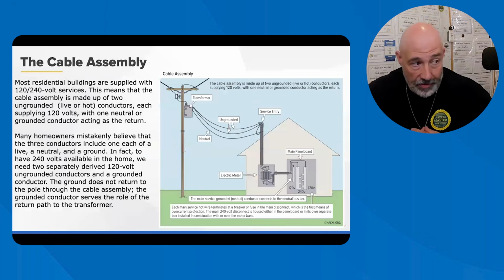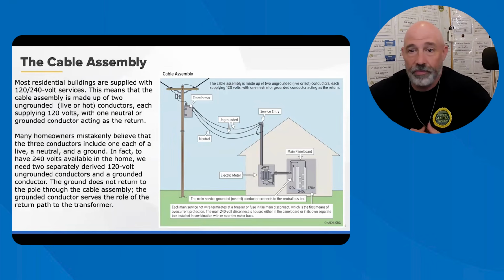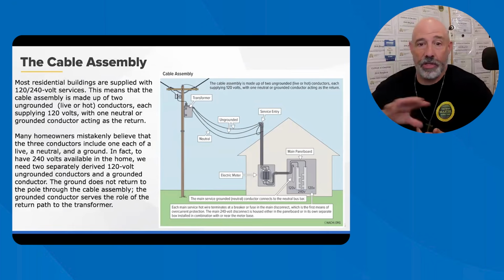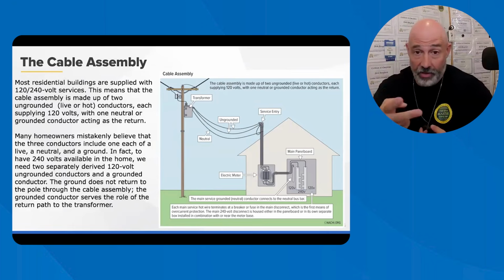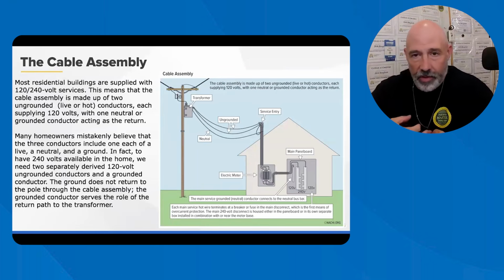Residential electrical services. Again, we're going to talk about this again. Most homes are 120/240 split phase service, and the service consists of two hot conductors and one neutral conductor. Each hot provides 120 volts, so you get 120 and 120, and together you get the 240. While both hots provide that, the neutral is the return path. Electricity always wants to find its way home, and the neutral provides that for it.